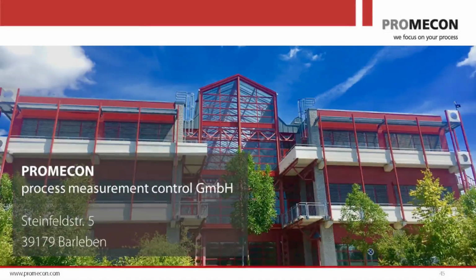Sometimes, of course, no, not sometimes, a lot of times, in power stations, you have bends. And behind the bends, you want to measure. Now, in most of the power stations that are existing today, there are some devices installed that usually have an existing duct modification in them. A duct modification would be an orifice, an aerofoil, a venturi, something like that. Now, those duct modifications we like to use because they usually act as flow straighteners. If you have a stratified profile after a bend and it hits a venturi, then in the shallow section of the venturi, the profile will be very flat. The venturi more or less forces the profile to be flat again because the air is accelerated. And the same thing you have with any other obstruction in the duct, with an airfoil or with any other.